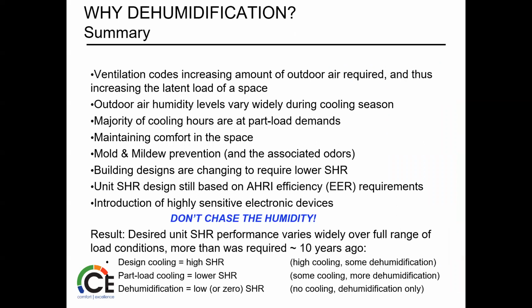So the biggest thing is a lot of guys try to chase the humidity in the building. They kind of go too much. Maybe they're overcooling, creating uncomfortable temperatures in the space. They try to change the operation of the unit, adjusting space temperature, humidity, all that stuff. The biggest thing is you just need a way to dehumidify that's not just an air conditioner. There are just spaces where an air conditioner isn't going to work. The up and down is too much.